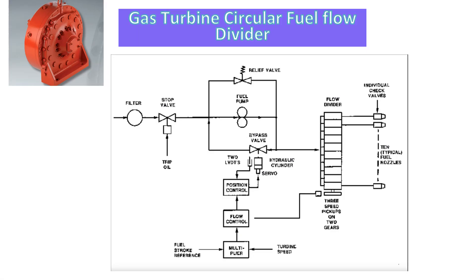Flow divider is an equipment shown here in this simplified sketch. Liquid fuel comes to the turbine and passes through a filter. Then there is a liquid fuel stop valve — when a turbine trip signal is received, this is the first valve which stops and cuts off the fuel supply. Then it goes to a fuel pump and there is a relief valve and bypass valve. And then it comes to the flow divider.